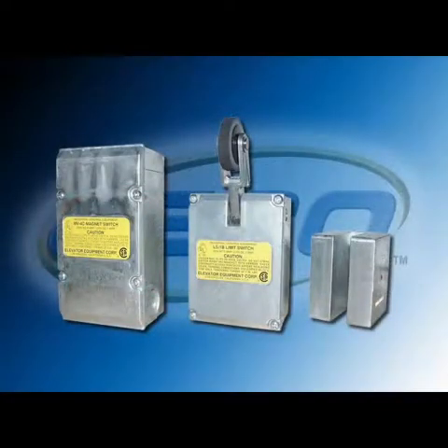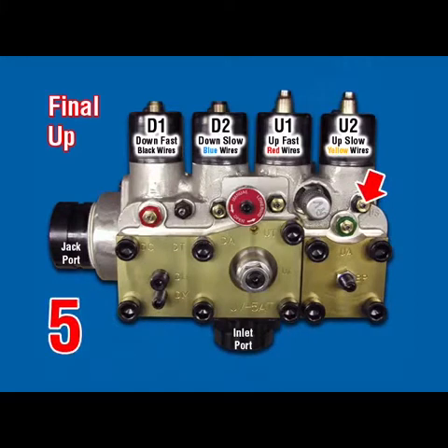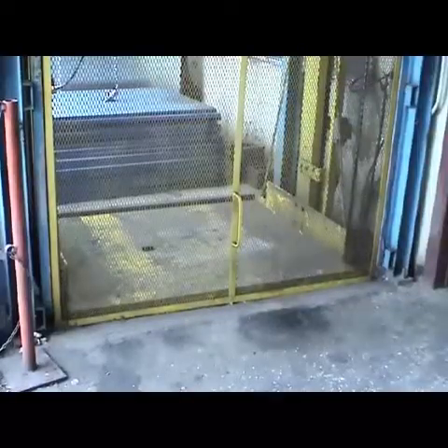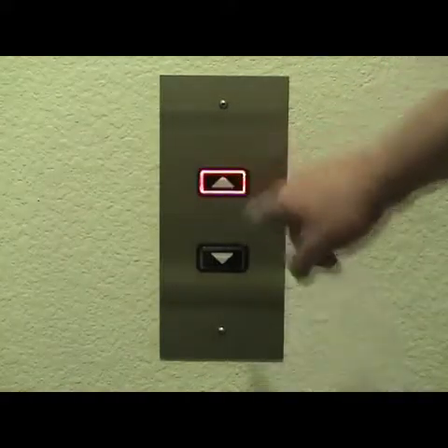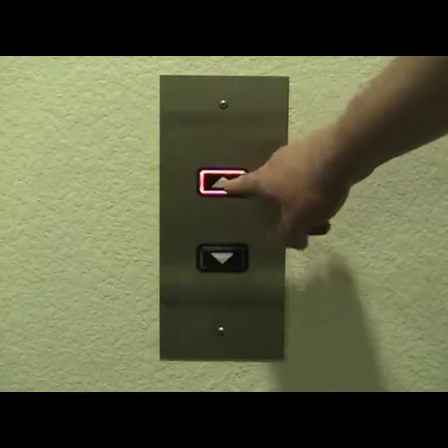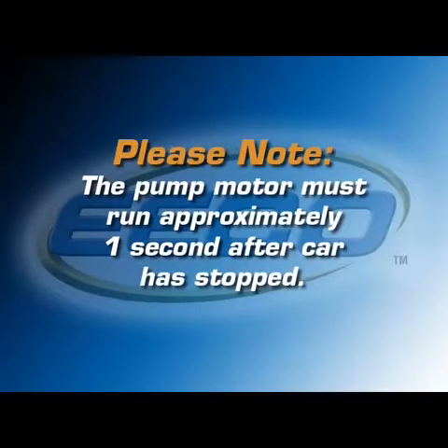Slow down switch should be located to give 3 to 4 inches of stabilized leveling. US Up Stop. The following procedure helps in cutting through the ineffective zone of the up stop adjuster, therefore expediting the final setting of US. Car at lower floor with no load. Disconnect U2. Register an up call — car should not move. Turn US clockwise until car moves, then counterclockwise until car stops again. Reconnect U2. Register an up call and observe up stop. Turn US clockwise for softer stop or counterclockwise for firmer stop. Please note the pump motor must run approximately one second after the car is stopped.